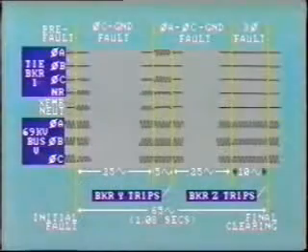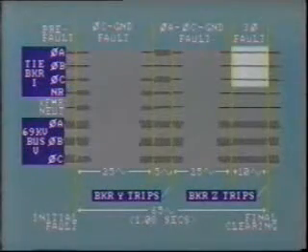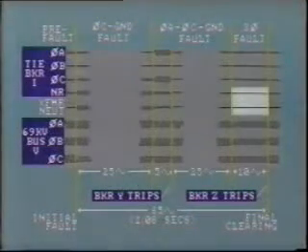For the next 10 cycles, we have a balanced three-phase fault. You can see this from the three fault currents in the tiebreaker and the fact that neutral and residual currents are now zero. Breaker Z at the other end of the faulted line now trips to completely clear the fault.